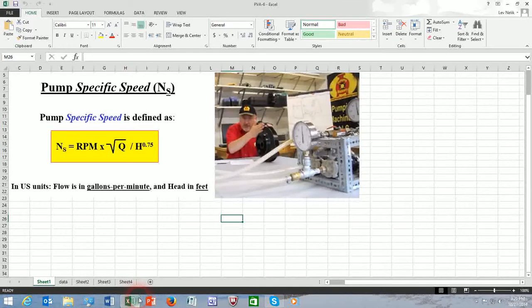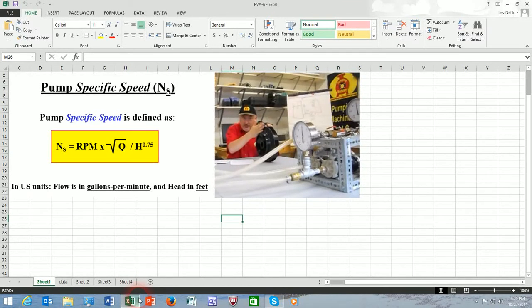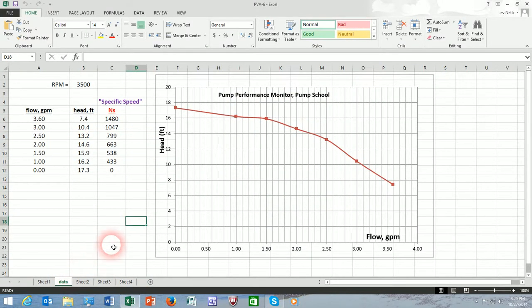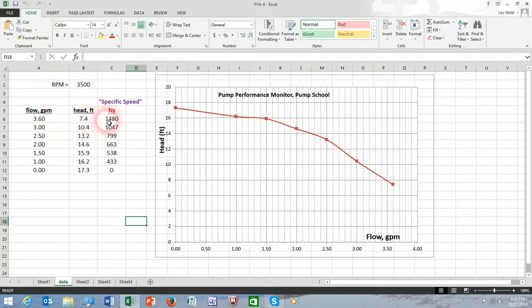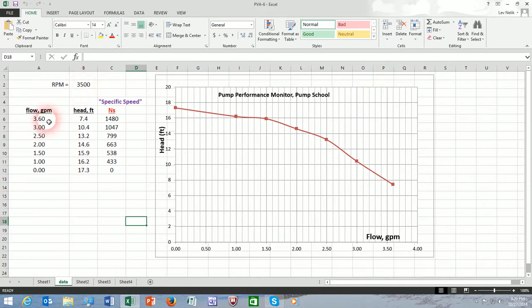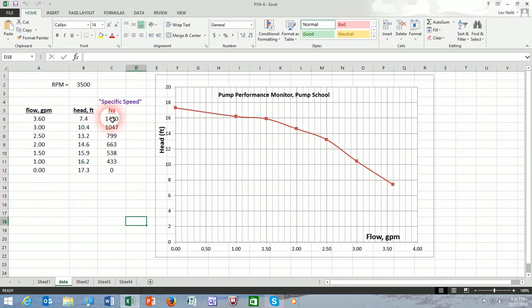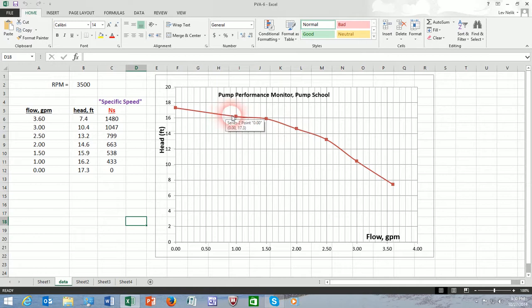So this is the definition of specific speed of the pump: RPM times square root of flow, divided by head raised to the power 0.75. We discussed that and we did the test. We produced seven test points, flow and head. And on each flow and head, we'll calculate its specific speed of the pump at 3500 RPM running test speed. So the flow was dropping from 3.6 down to 3 and then to zero, eventually to zero. So we have several sets of calculations for head and specific speed. And as we can see, the values of specific speed vary very substantially depending at which point along the curve we choose to pick flow and head for calculation of specific speed.